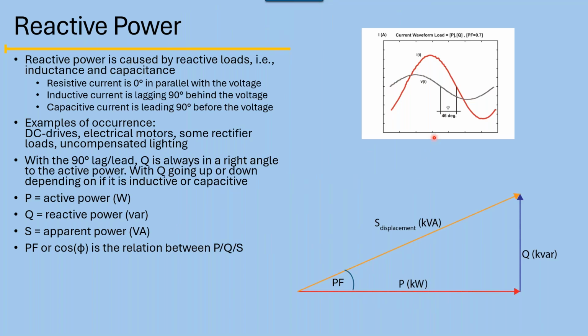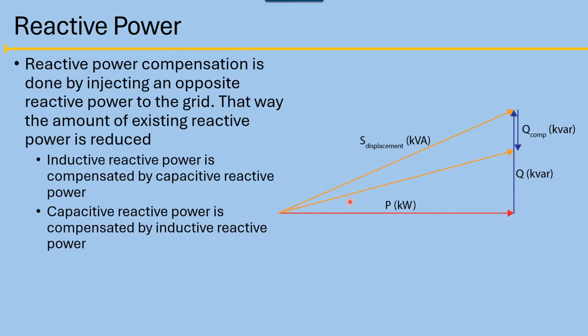Here I've got an example of voltage, and the current is lagging the voltage by 90 degrees. Because of that, you have what's called power factor. Power factor is kW over kVA. And of course, a motor is an inductor, so how do we correct it? We add capacitance. When we add capacitance, we can lower this and get the kVA closer to the kW, so we make a more efficient system because we're lowering the amount of current.